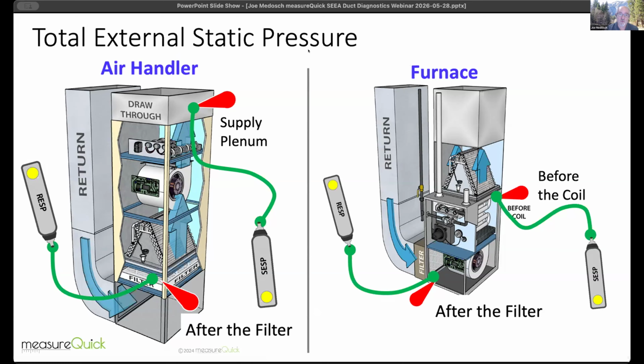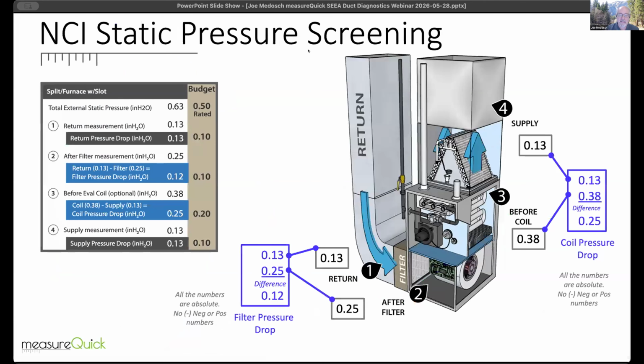This is part of what the TrueFlow grid is doing also. If you want to kill 2 birds with 1 stone, the TrueFlow is going to give you these similar measurements plus more. They're going to do more of a screening. This is built into the NCI screening, which is in MeasureQuick. This is also in the TrueFlow grid app itself. You can do a static pressure screening by itself, just static pressure. If you didn't have the grid, you can still do great diagnostics with their app, or with MeasureQuick. These are all free options that are in both our apps.